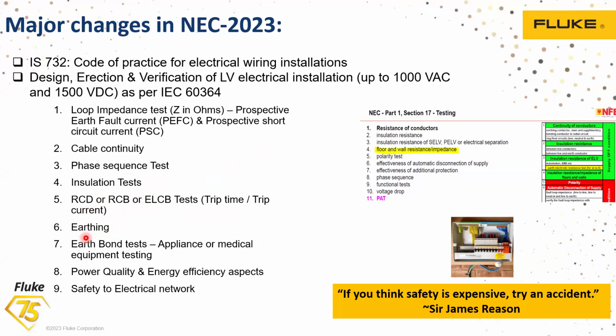Regularly check the earthing, that is the loop impedance, how much resistance is available, and other tests like the earth bond test on appliances, or testing of medical equipment. Then regularly check the power quality, the efficiency of the equipment and the safety of the electrical network. If we care about safety, we have to ensure that all these tests recommended by the standards are done regularly, at regular intervals of time.